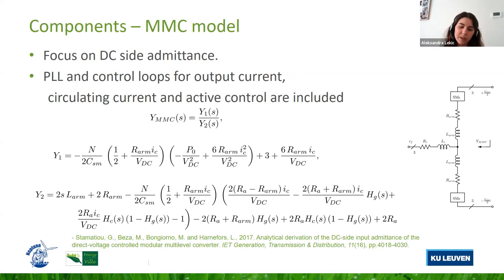It is considered like an impedance described with this formula, so you can see the formula for the admittance of an MMC looked from the DC side. In further work, what we have at the moment is an MMC model that can be described with admittance looked from the AC side in the DQ frame, also from the DC side, and all the interconnections between DC and AC sides are now supported.